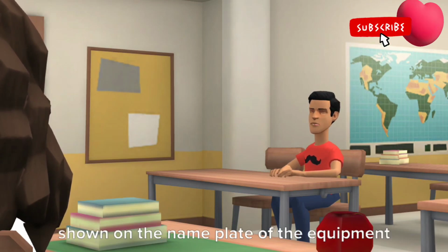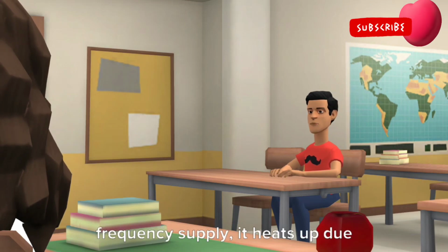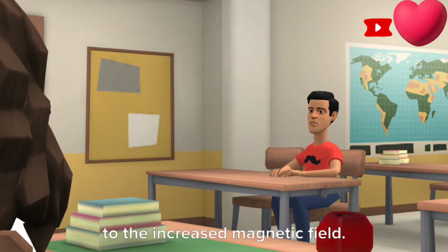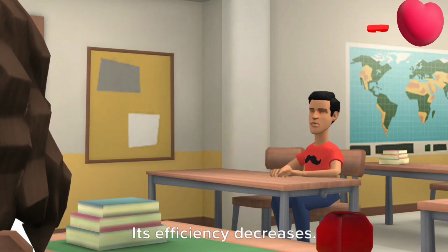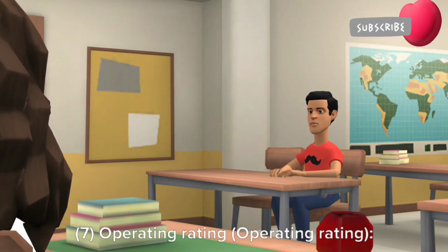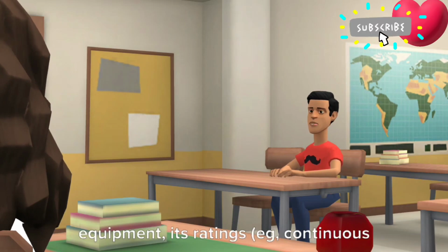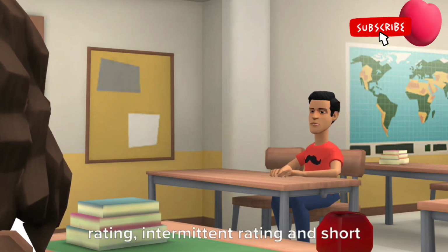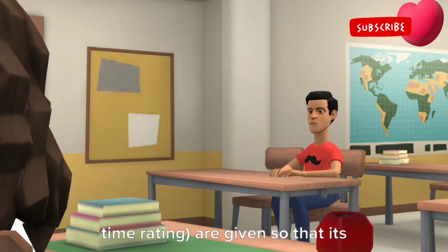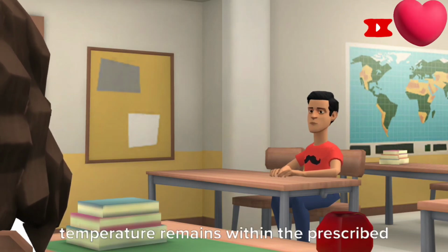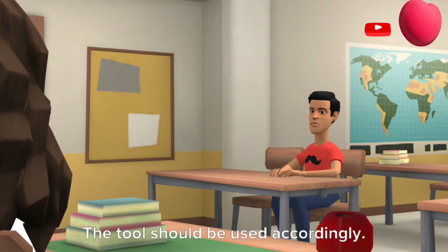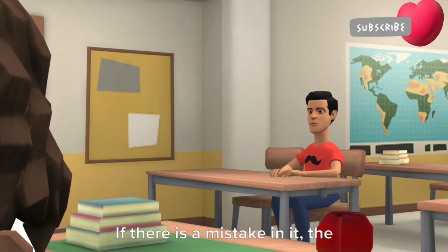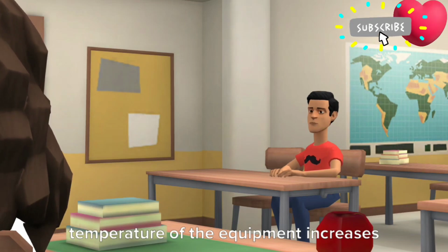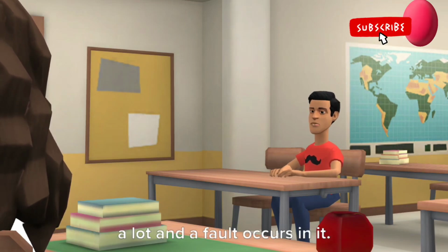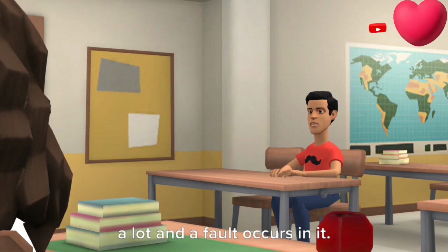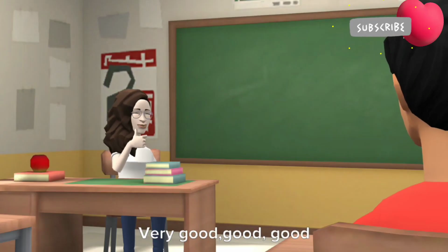6. Frequency. Operate the equipment only on a supply having the frequency shown on the nameplate of the equipment. If it is driven from a lower frequency supply, it heats up due to the increased magnetic field. Its efficiency decreases. 7. Operating rating. According to the capacity of each equipment, its ratings, for example continuous rating, intermittent rating and short time rating, are given so that its temperature remains within the prescribed limits. The tool should be used accordingly. If there is a mistake in it, the temperature of the equipment increases a lot and a fault occurs in it.